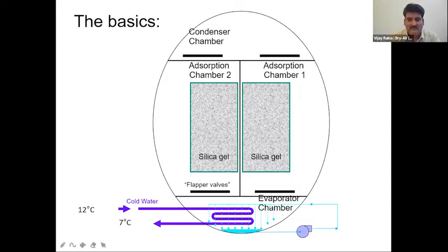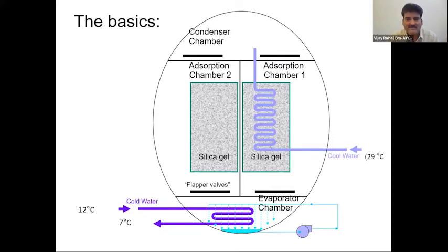Once it gets evaporated, we have to transfer this refrigerant vapor from the evaporation chamber to the condenser, and we are doing this through silica gel based technology, where silica gel is a solid material which adsorbs the water vapors on its surface. So you see the 29 degrees is the cooling tower water. When the cooling tower water enters chamber 1, it is a cold chamber, pressure is low.